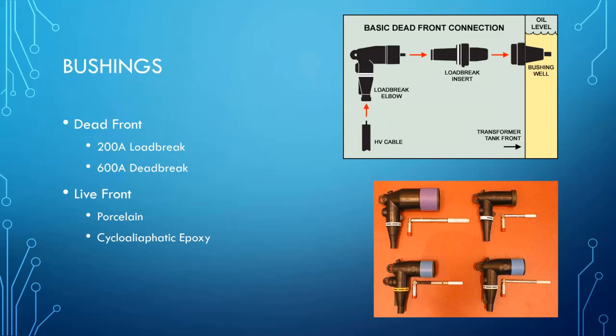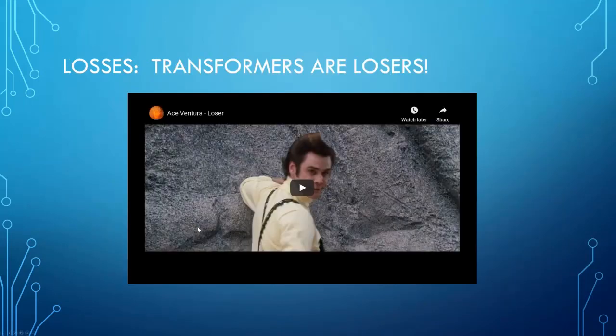On the live front side, we have really seen porcelain almost go away. There are still customers that specify porcelain. It's getting very, very hard to get porcelain high voltage bushings. Cycloaliphatic devices are just easier to manufacture. They have superior performance in a lot of different ways. What I've shown here to the right are some load break elbows. They're made by a lot of different manufacturers, Elastimold, Cooper, 3M. And those are the elbows you use to make a dead front connection. Let's see if this video will play. Transformers have losses, and therefore transformers are losers.